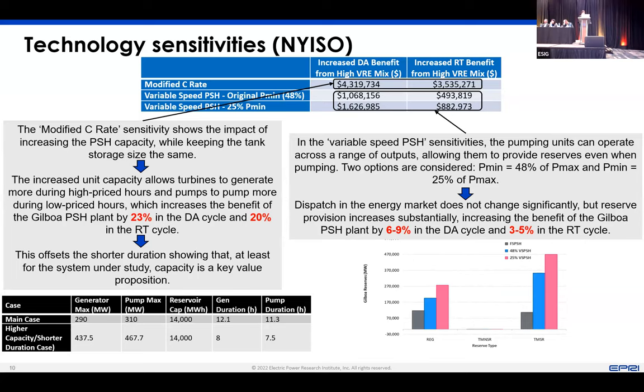And then the second one is the variable speed pump storage sensitivity that we ran. So in the base case, the plant is a fixed speed pump storage. And what that means is that in the pumping mode, it's either on or off. It can't really operate at all points of its operating range. Now, variable speed, now that we allowed it to do that, one of the key things that changes is it can now bid into ancillary services and provide ancillary services where it previously couldn't.